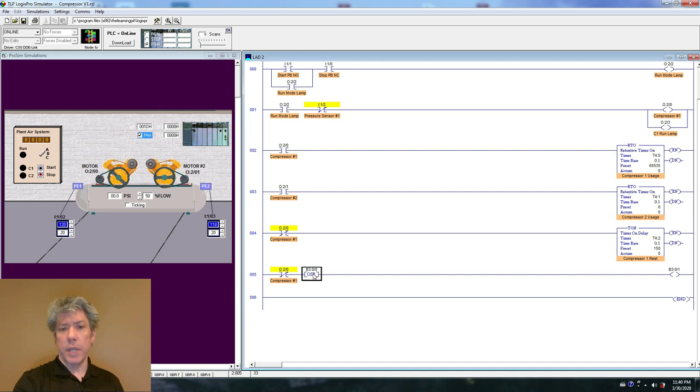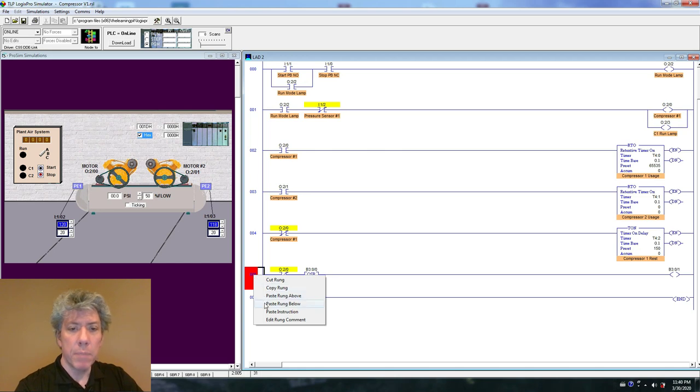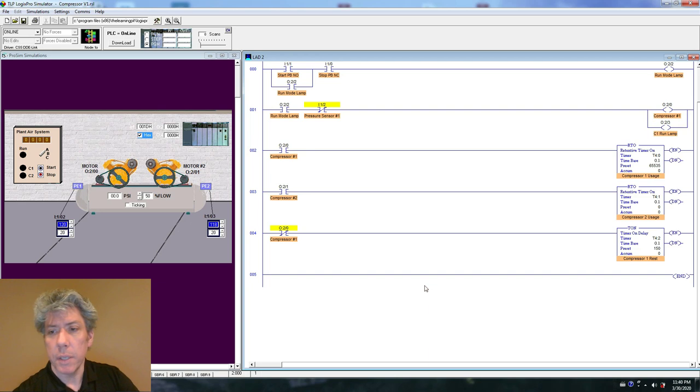So really all I had to do was put a one shot on this row. And then what will happen is when the compressor shuts off, this timer will run. Well, that won't work, will it? Because if I do that, I have to pre-select. If I do that, then what I really want is to lock in this timer and make it run. So maybe this is not needed at all. Maybe all I really need to do is wait until the compressor shuts off and use that to prevent the compressor from coming on until the delay is done. Yeah, I think so. So all that stuff with one-shots, that was interesting and useful, but maybe I don't need to use it. I may come back to it later. I don't know. Let's see. So maybe I don't need to do edge detection after all.